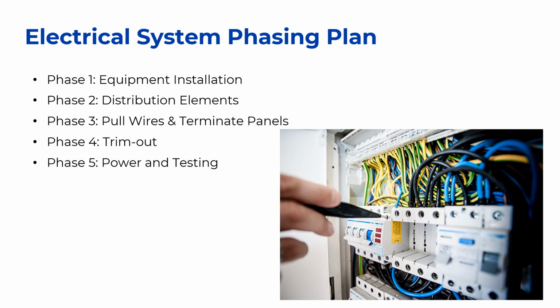The second phase, which is the distribution elements, is where the distribution of the electrical elements is placed. In this phase, all elements such as switchboards and panel boards, wiring trays, disconnect switches and junctions are installed. Third phase is the pull wires and terminate panels. This is where, before the sheetrock is placed, all wires are pulled to place and most panels are terminated. The fourth phase is the trim out, in which all accessories, fixtures, and utilization equipment are installed and connected to the building's electrical system. By the end of this stage, the entire electrical system of this building should be working efficiently.